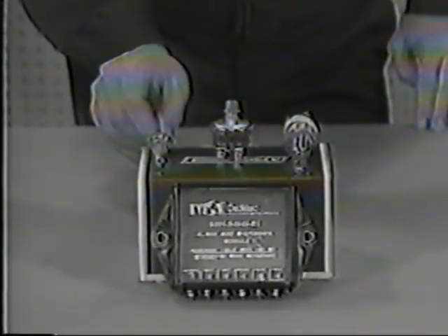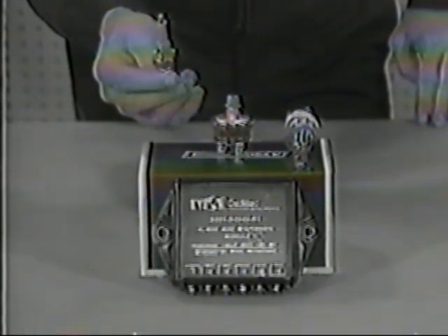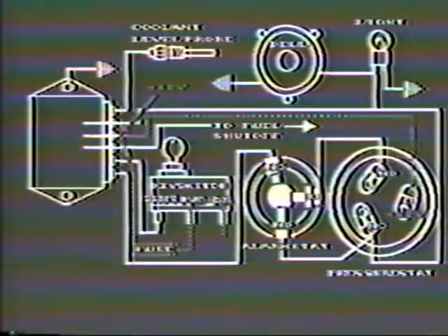Let's turn now to the third alarm and shutdown engine protection system, the Series 9031 three-way. 9031 has a feature not found on 9032 or 9033, low coolant level alarm and shutdown. To accomplish this, 9031 uses the same coolant level probe that we saw when we were looking at alarm-only engine protection systems. The system begins at module terminal number 4, where the key switch circuit is connected.